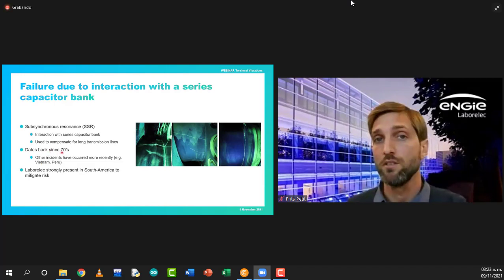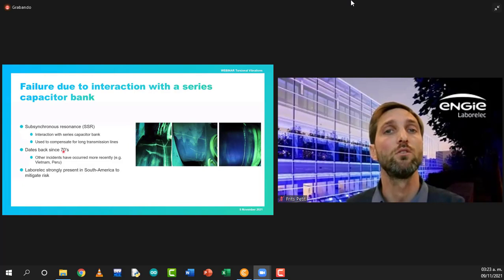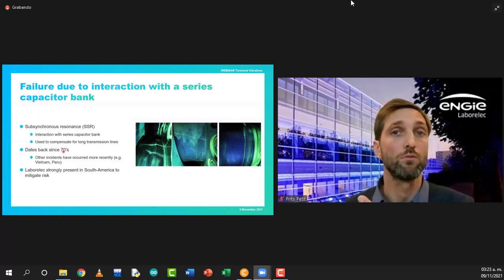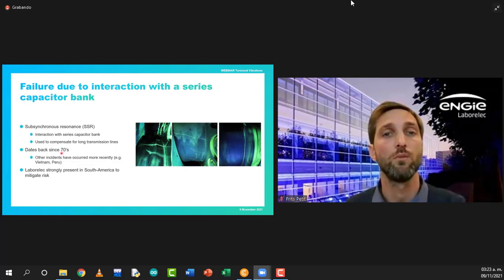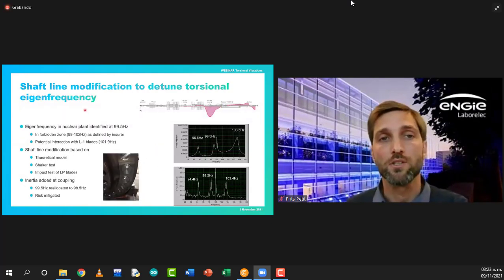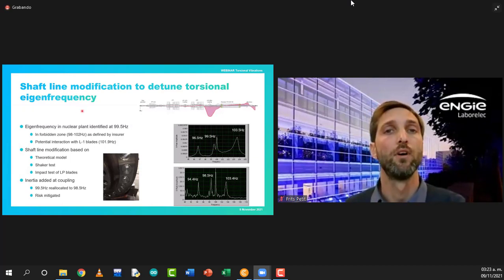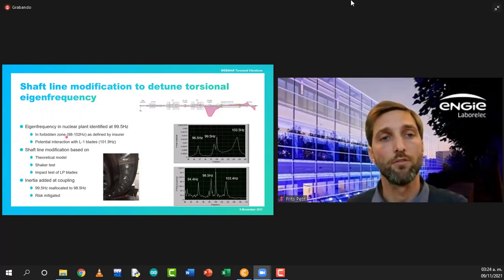The phenomenon dates back from the 70s. It's well known, but it's not always taken into account in the design stage, or there might be some changes in the grid configuration which render the system unstable while it was stable before. Another example which is well known also typically in the design stage is excitation at twice grid frequency. So when you have a shaft line connected to grid, you will always have excitation at once and also at twice grid frequency. So this means 50 and 100 Hertz or 60 and 120 Hertz. So by design, you want to avoid that you have natural frequencies, torsional natural frequencies in that range. So typically you have a forbidden zone.